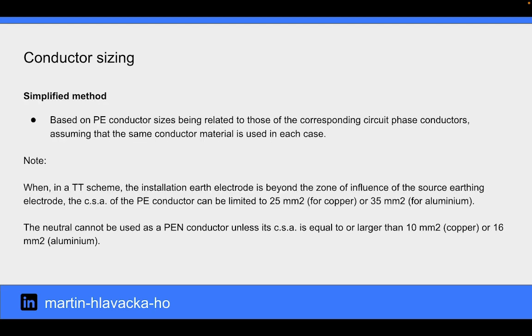The second method is the simplified method, which is based on PE conductor sizes being related to those of the corresponding circuit phase conductors, assuming that the same conductor material is used in each case.